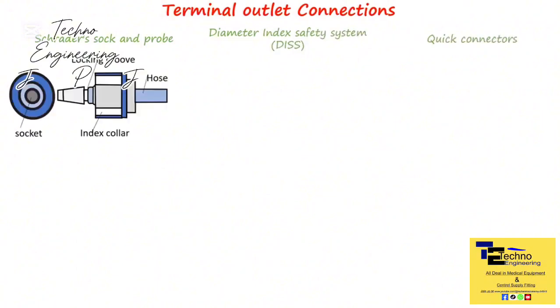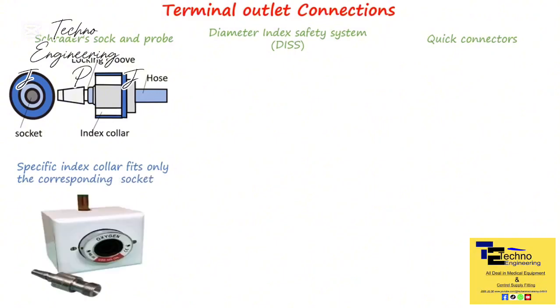Several safety mechanisms are in place to prevent incorrect gas connections at terminal outlets. These include Schrader's probe and socket connection, the diameter index safety system, and quick connectors. The Schrader probe features a gas-specific index collar with a unique diameter that only fits the corresponding socket for that gas type. For instance, an air hose cannot be connected to an oxygen outlet. The socket is color and shape coded to match the intended probe.